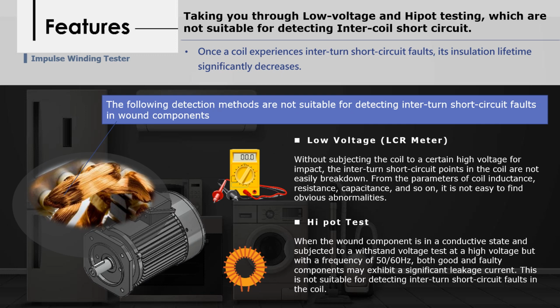As we dive into the world of impulse winding testing, the importance of insulation reliability for wound components like inductors, transformers, and motors becomes paramount. With the rise of new energy, electric vehicles, photovoltaic industries, and advancements in power technology, the demand for the safety and reliability of wound components has increased. Typically, component manufacturers use a hipot tester to check the voltage resistance and insulation capabilities. However, these tests often overlook layer-to-layer short and short-circuit issues caused by defects in the winding wire, such as scratches, fractures, or incomplete short circuits.